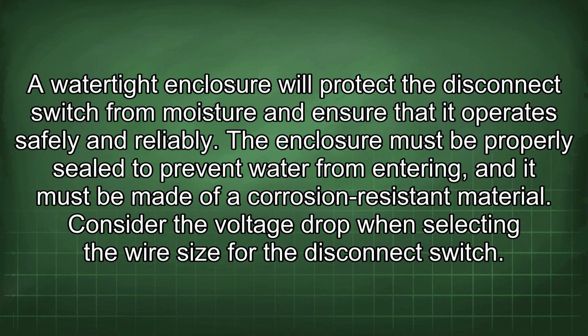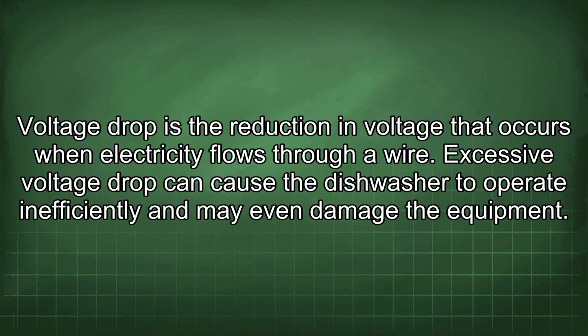Consider the voltage drop when selecting the wire size for the disconnect switch. Voltage drop is the reduction in voltage that occurs when electricity flows through a wire. Excessive voltage drop can cause the dishwasher to operate inefficiently and may even damage the equipment.